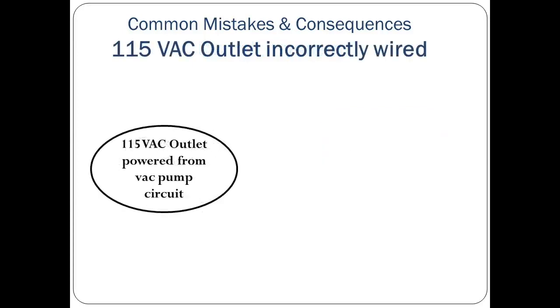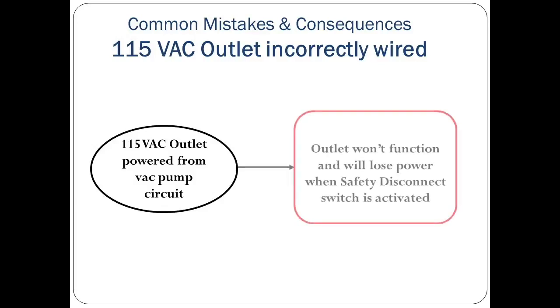We have seen the 115-volt outlet powered from the vacuum pump circuit. This could result in two problems. One, insufficient current to the outlet rendering it useless, or two, if the safety switch is engaged, the outlet will receive no power. Remember that the outlet is there to aid in the completion of any testing and maintenance task, so it is important that it is not dependent on the safety disconnect switch for power.